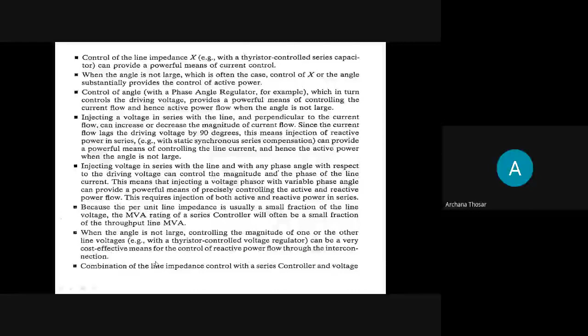When the angle is not large, controlling the magnitude of one or the other line voltages can be a very cost-effective means for controlling reactive power flow through the interconnections. These are some parameters by which changes give you maximum power transfer over the transmission line.